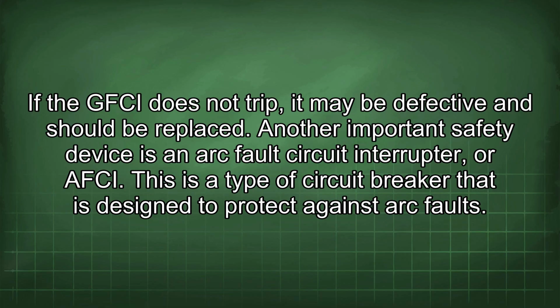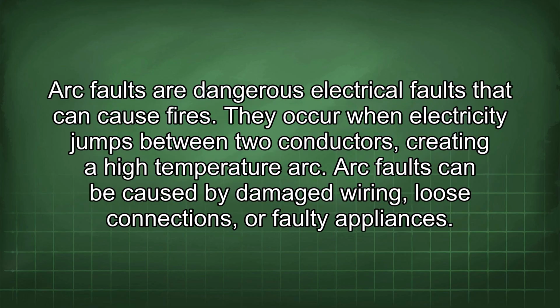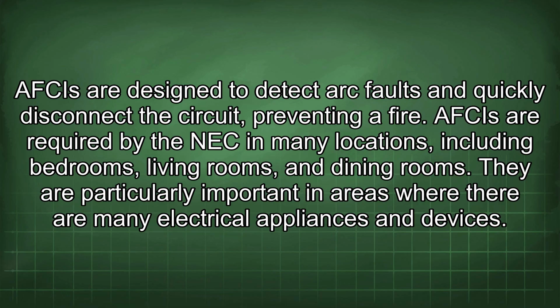Another important safety device is an arc fault circuit interrupter, or AFCI. This is a type of circuit breaker that is designed to protect against arc faults. Arc faults are dangerous electrical faults that can cause fires. They occur when electricity jumps between two conductors, creating a high-temperature arc. Arc faults can be caused by damaged wiring, loose connections, or faulty appliances. AFCIs are designed to detect arc faults and quickly disconnect the circuit, preventing a fire. AFCIs are required by the NEC in many locations, including bedrooms, living rooms, and dining rooms. They are particularly important in areas where there are many electrical appliances and devices.